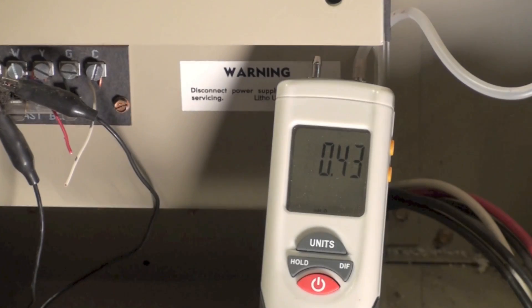As with any pressurized combustion chamber, when you adjust manifold pressure you got to put the cap back on before you test the pressure, or your measurement will be incorrect. And that's the pulse.